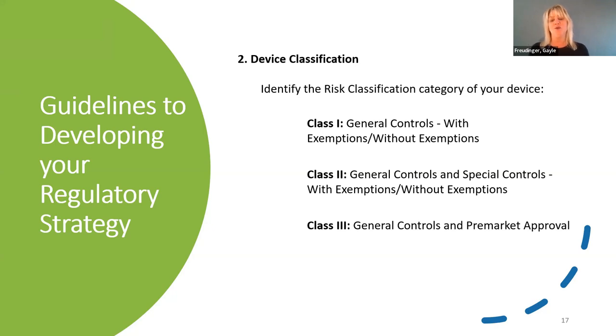Device classifications are grouped according to medical specialties. There are 16 groups and they follow 21 CFR 862 to 892. So you're going to want to identify the class and the appropriate product classification. This will help determine the approach you need to take in terms of the regulatory guidelines. Once you've identified that class, you can start thinking about the regulatory submission you need to work on. This will also define the length and duration of testing and impact your timeline. So this is very critical.